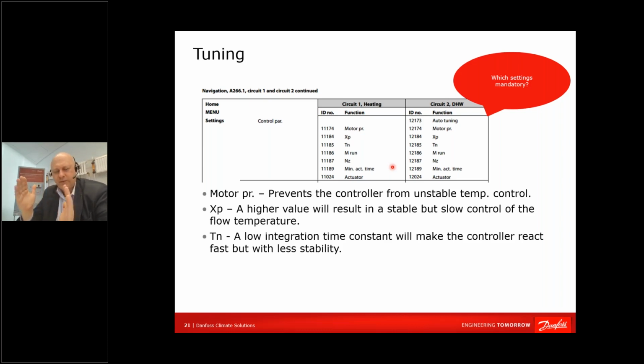XP is measured in temperature, and the smaller the XP value you enter, the sharper the ECL will work. For example, if you set XP to 1 degree, then when your temperature goes out of this 1 degree range, ECL will send an immediate signal to compensate it.